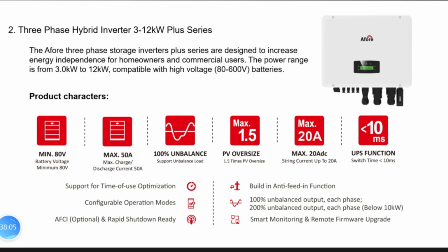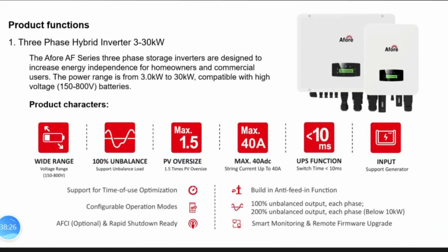Question: This plus series seems to be able to start with a lower battery voltage than the standard version. Is this true? Yes. All these three-phase hybrid inverters need to connect with a high voltage battery bank. Here you say 80 to 600 volt batteries, so the starting voltage is 80 volt. Yes, and for the standard series it's higher, the standard one is 150. So the plus version is 80. So if you have two battery blocks, 50 volt each, you have around 100 volt. So you can do it with the plus series, but not with the standard.